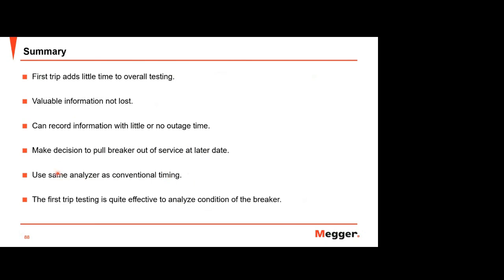Some countries, like Malaysia and Vietnam, are really concerned now at medium voltage level to combine conventional testing and first trip testing. So they can do a comparison afterwards to see which breakers should continue with the conventional test or just be kept energized as normal. So I can say the first trip testing is quite effective to analyze the condition of the breaker. I think I conclude my presentation today.